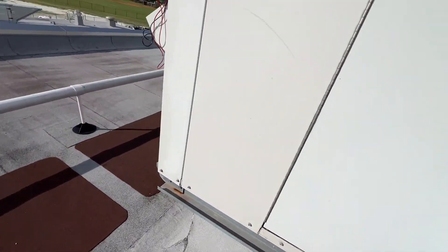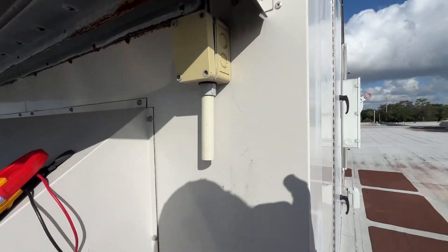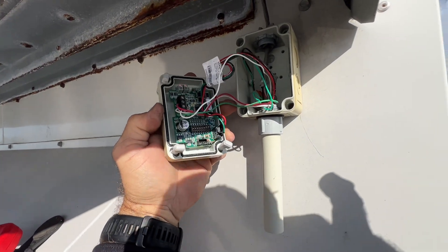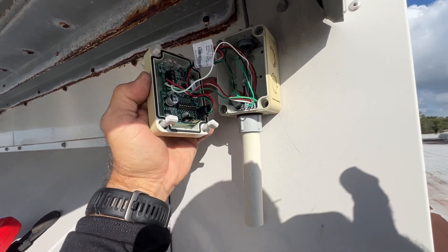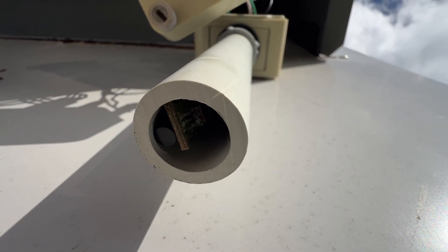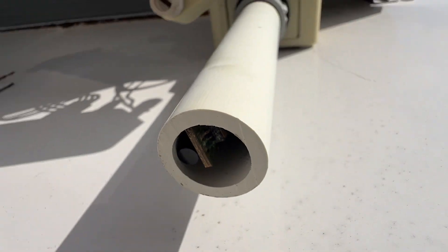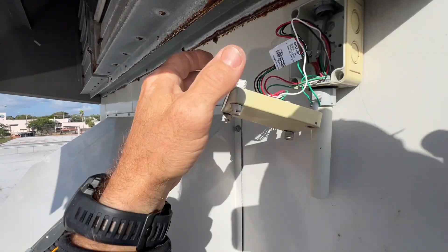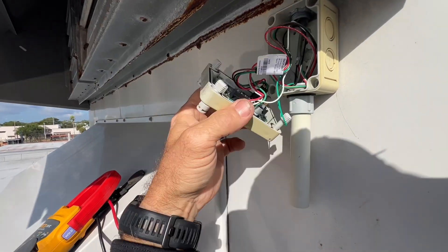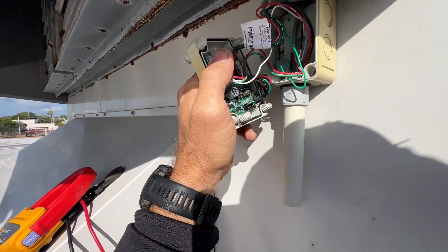Let's do our sensor — I'll just open it up and look. Everything looks good, you can see where the actual sensor is. It's a bit corroded in there, so I'm going to order up a new sensor for this. I did have voltage here but nothing coming out.